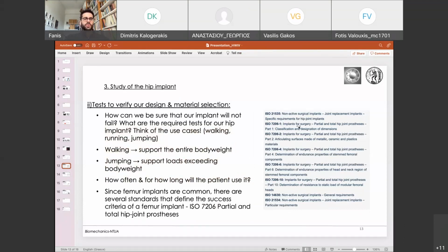Also, something to consider is that because you're dealing with medical devices, a medical device needs to be certified before it can be used. Certified means that a regulatory or notified body, an organization anyway, will come and audit you and check your files and the experiments you perform on your medical devices.